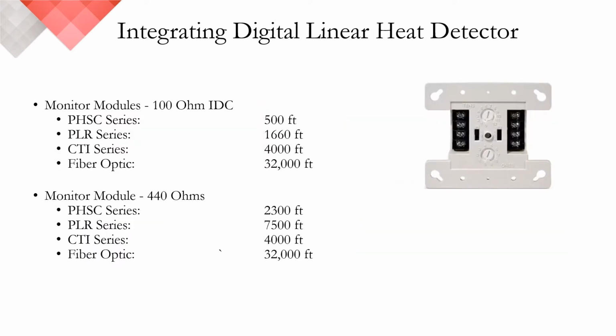As I referenced in the previous slide, integrating linear heat onto other manufacturers' control equipment can become something of a challenge, depending on some of the electrical values of the equipment we're connecting to. Linear heat detection is capable of being supported through any initiating device circuit, regardless of manufacturer. Where the challenge lies is the output value of the IDC and how much linear heat can be supported directly. As I mentioned before, steel has an inherent resistance value of 0.185 ohms per foot, and adding copper reduces this value to 0.058 ohms per foot.